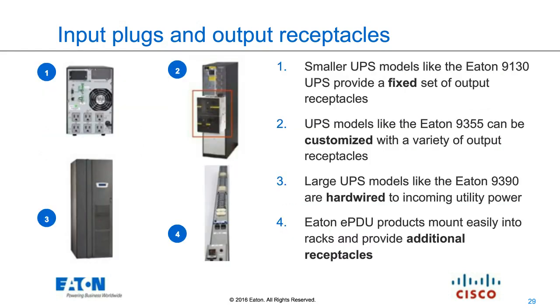From a UPS design consideration, the same consideration for plugs and receptacle types must be taken. We have a couple of different approaches to the flexibility of receptacles. Under 3 kVA, the UPS is going to have the receptacles it comes with, and that's across the market, not Eaton specific. But as we get into higher density solutions with larger UPSs, there's larger flexibility for customization. We can put the outlets that are needed on the UPS so you don't necessarily have to bring in an electrician to run custom circuits to the rack. You'd just bring the necessary power to the UPS, customize the outlets, and run your PDUs straight over from the rack into the UPS, reducing the overall installation cost.